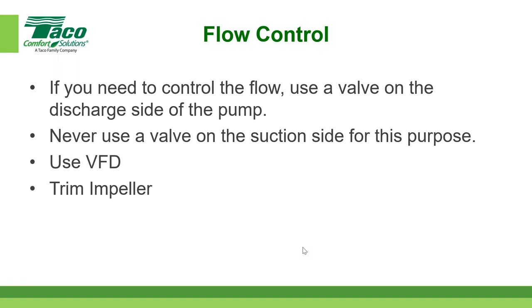And here's some basic stuff here. If you need to control the flow, use a valve on the discharge side. Never put it on the suction side. Never, ever control the flow with a valve on the suction side. Shut off valves, that's one thing, to isolate the system, but don't control flow with a valve on the suction side. That's just going to cause issues of air getting into the pump. Or you can use a VFD or trim the impeller, right?